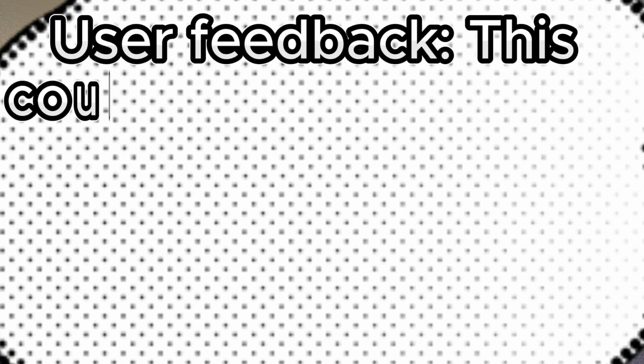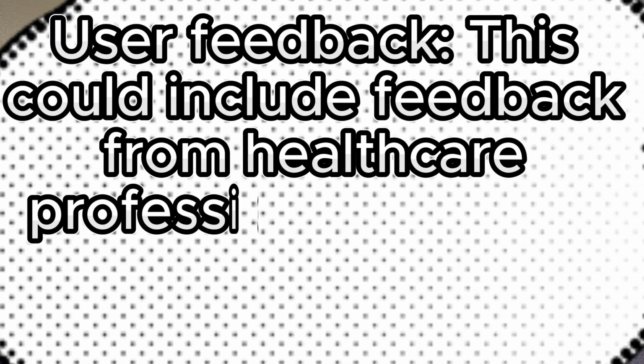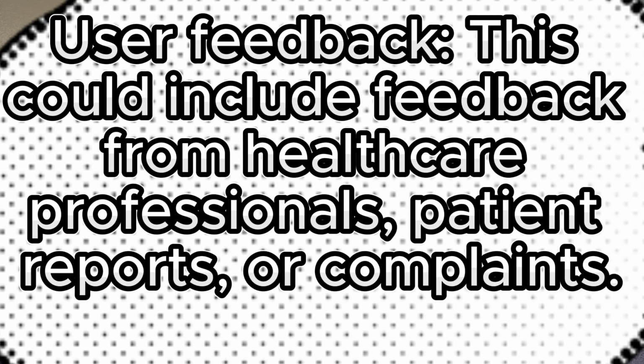And the second post-production activity you need to do is user feedback. So this includes feedback from healthcare professionals, patient reports, or complaints, right? For example, if you're a manufacturer of surgical robots and you receive a complaint that the robot is malfunctioning during the surgery, for example, if it's supposed to cut here, but it's actually moving 2 inches automatically without telling it, right?